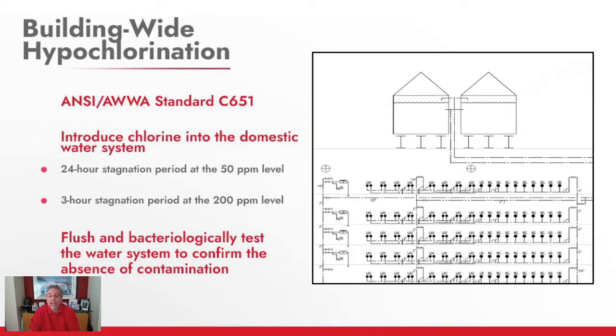If you've serviced your tank and it's been cleaned and disinfected, but you still come up with positive water samples, a building-wide hyperchlorination would be in order. This is basically chlorinating the entire building system in accordance with ANSI standards, which gives you two options: a 24-hour stagnation period at a low chlorine level, or a much more aggressive approach at a very short period of time with a much more concentrated level of chlorine.